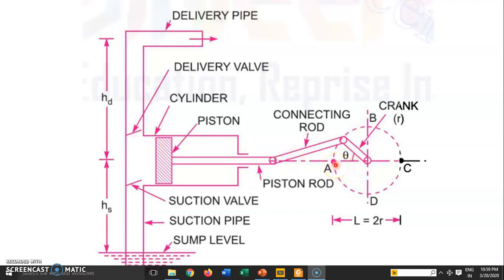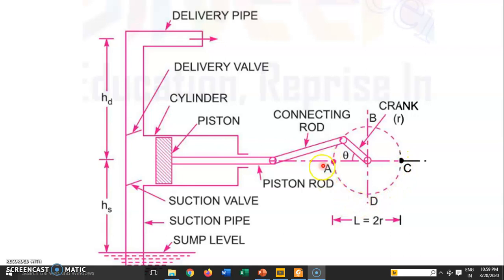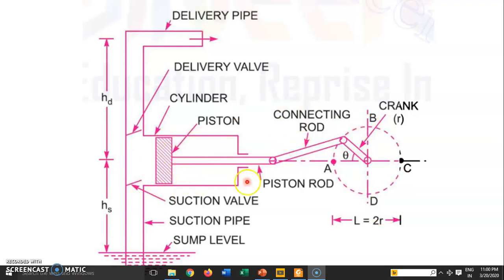When the crank moves from point A to point C, the piston goes from left to right — that is the suction stroke — and no water is discharged through the delivery valve. When the crank moves from point C to point A, the piston moves from right to left — that is the delivery stroke — and water moves through the pipe. So water is delivered only during the delivery stroke. For one complete rotation, the discharge volume is area of cross-section × stroke length (A × L).